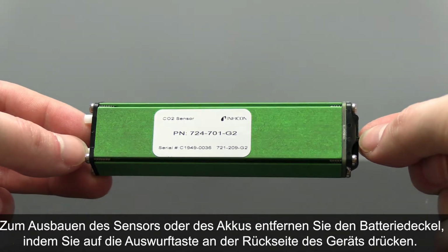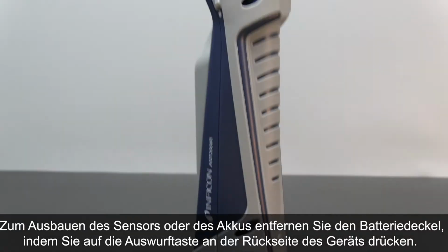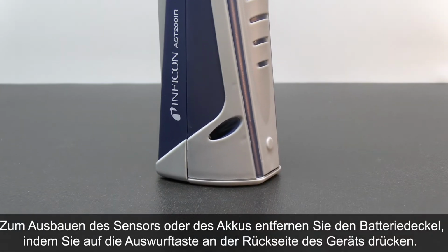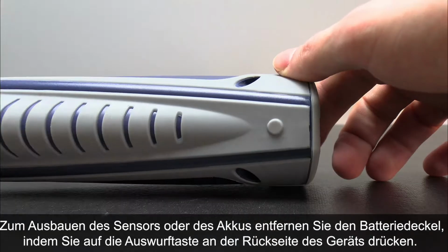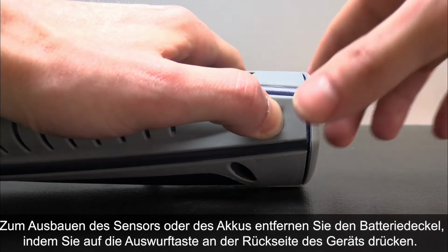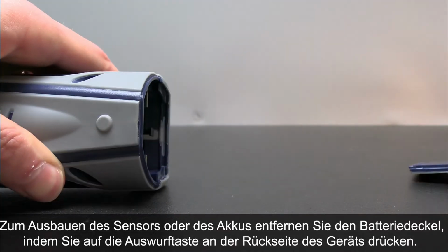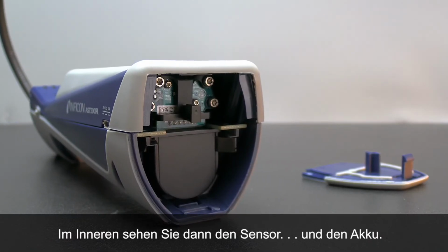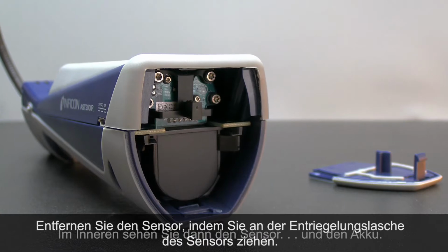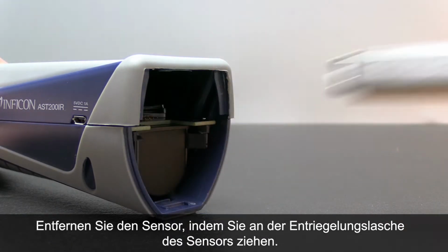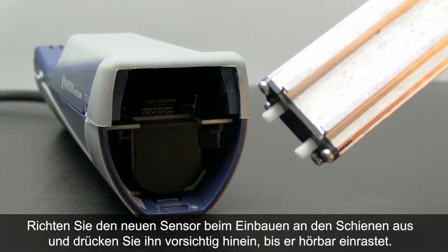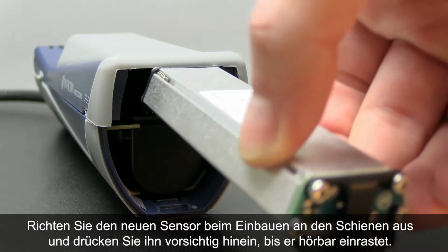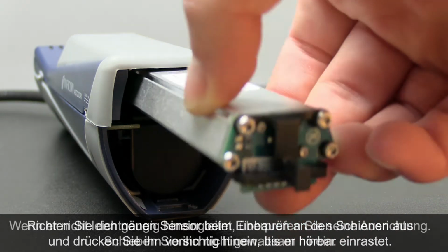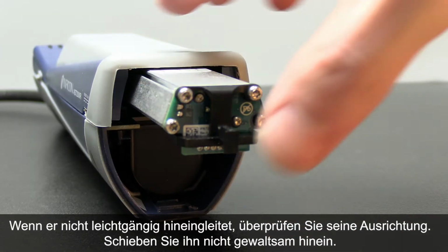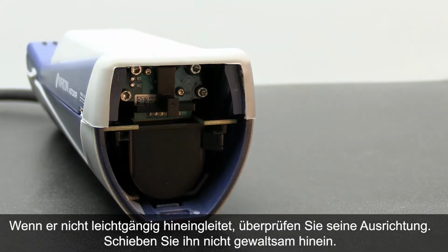To replace either the sensor or the battery, remove the battery door by pressing the eject button on the back of the unit. Inside, you'll see the sensor and the battery. Remove the sensor by pulling on the Sensor Release tab. To install the sensor, line it up with the rails and gently push it in place until it clicks. If it doesn't slide smoothly, check the alignment. Don't force it.